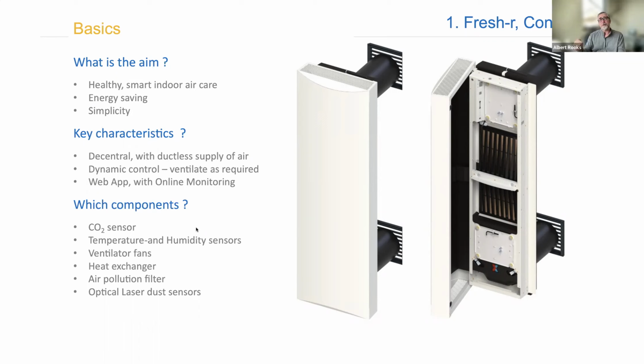We've got a built-in loss with heat recovery. It's not 100% recovery, it's 80% recovery, right? So there's always a 20% loss or a number like that. So the only reason we need to run the fan rate is we need to manage CO2 for people, or we need to manage humidity. And it's got an onboard humidity sensor also. So in the condition where there's lots of inside humidity, it can increase the rate and blow the humidity out. In a condition where there's lots of outside humidity, it'll see that. It'll lower the fan rate to reduce the amount of humidity coming in.